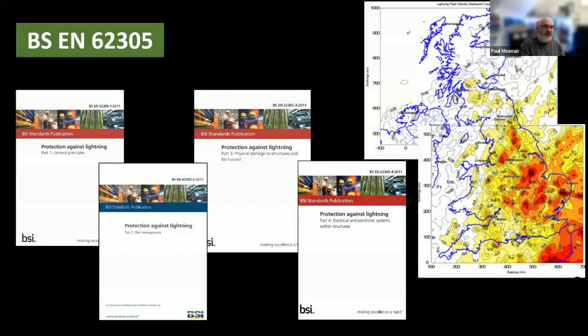Now in England, just coming back on the HV side, we have something called atmospheric transients, lightning protection, and we have four BS EN standards, 62305. Part one is your general fundamental principles, part two your risk management, three the physical damage to structures and life hazards, and then four the electrical and electronic systems within the structures. Now in England, we do a risk assessment. We use the guidance. As you can see on the screen, we use flash density maps, where the weather services record all the lightning strikes so that we can ascertain the level of risk and design a proportionate lightning protection system. So lightning protection systems are risk-based. If you have a risk assessment, then you will design from the risk assessment. If you don't have a risk assessment, then in England, you'll be told to go away and look at 62305.